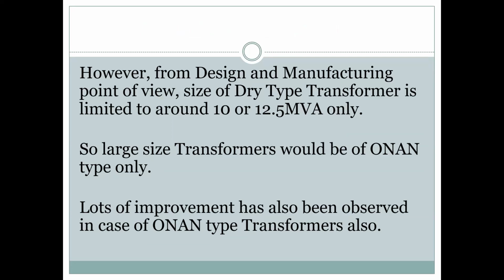However, from the design point of view, it has a limitation. It can go maximum up to 10 to 12.5 MVA and up to a 33 kV class transformer. So large transformers now have to be oil type only, and they have to be installed in the switchyard. Lots of improvement is also observed in the case of oil type transformers. We have tried that. Next.